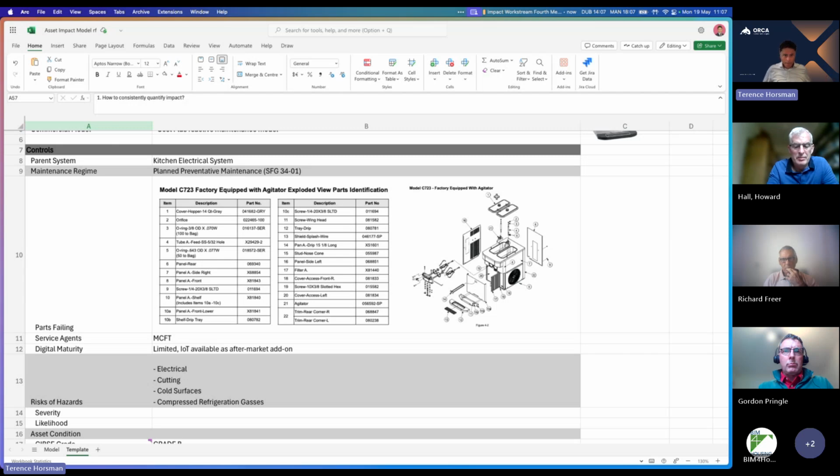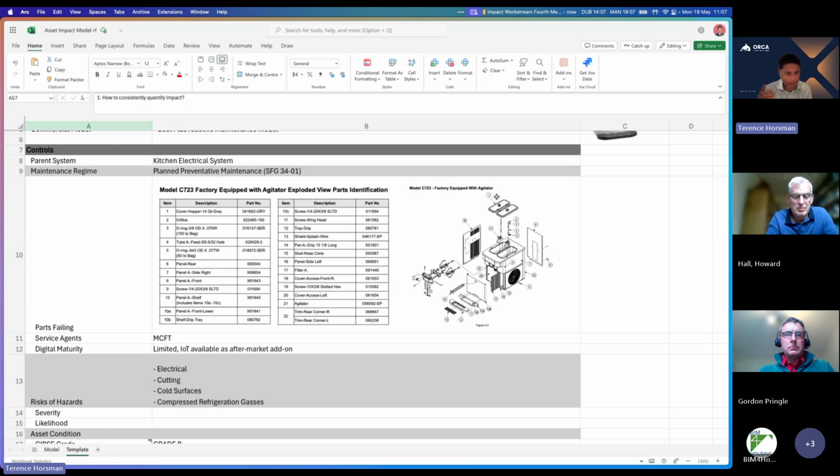We actually ran some data analysis over the last 5 years on what type of parts are most consumed against these assets. And what we're finding is some form of compressor changes against the heat pump. And we're finding something called a tune-up kit, where you're actually replacing a number of different components. That's a scraper blade, motor components, and the manufacturer also recommends this to be replaced every 5 years to extend the life cycle of the asset. But it depends on the usage cycle against that particular asset.